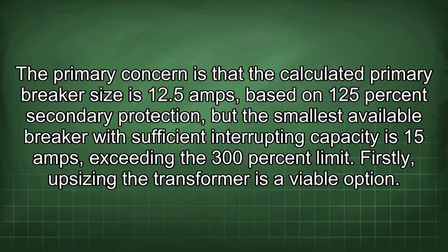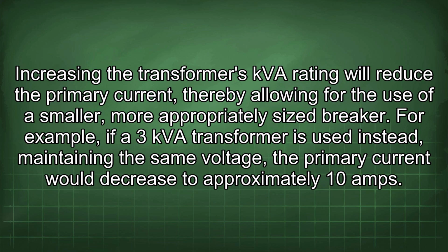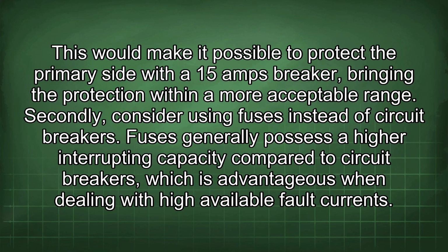Firstly, upsizing the transformer is a viable option. Increasing the transformer's kVA rating will reduce the primary current, thereby allowing for the use of a smaller, more appropriately sized breaker. For example, if a 3 kVA transformer is used instead, maintaining the same voltage, the primary current would decrease to approximately 10 amps. This would make it possible to protect the primary side with a 15 amp breaker, bringing the protection within a more acceptable range.